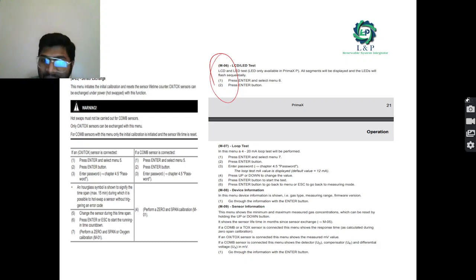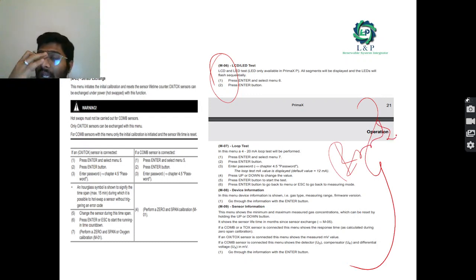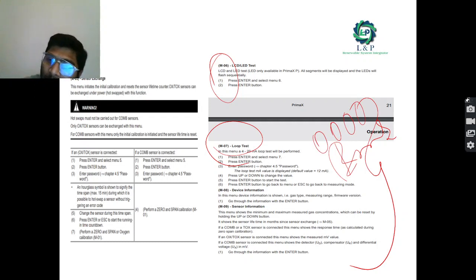And if you want to do the loop test, this is a very important test for other BMS engineers. If you want to test the 4 to 20 milliamps output from the concerned devices, you can go inside the menu 7. Okay, press the enter and put the password 0000, and the loop test milliamps value will be displayed. Okay, the default value is 12 milliamps. Okay, and you can increase or decrease through the up and downward arrows. Okay, and what else you can do is that you can press the enter button to start the test. Okay, once it is done, if you want to go back to the menu, use the escape button.